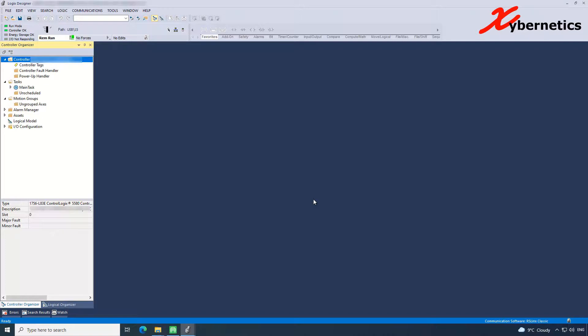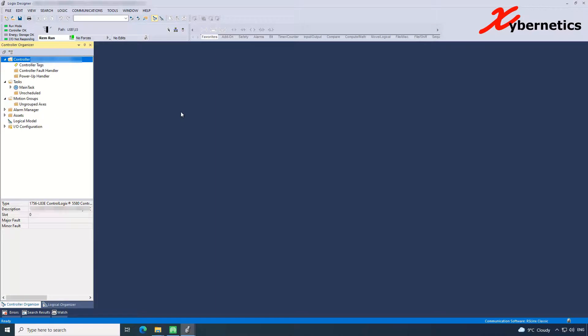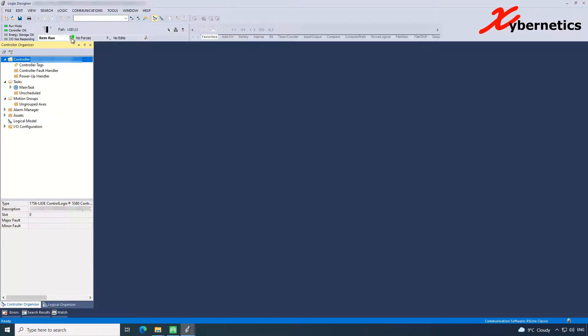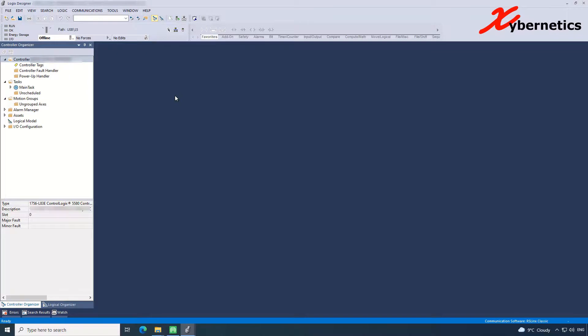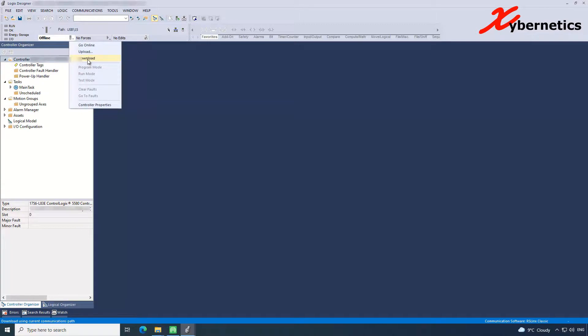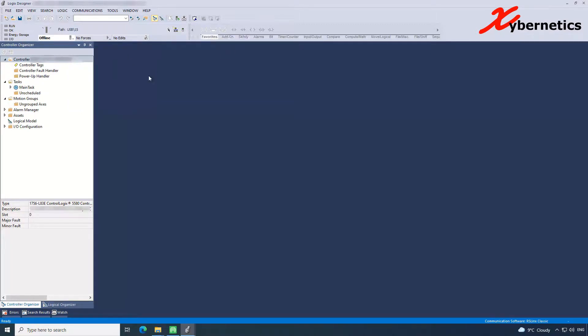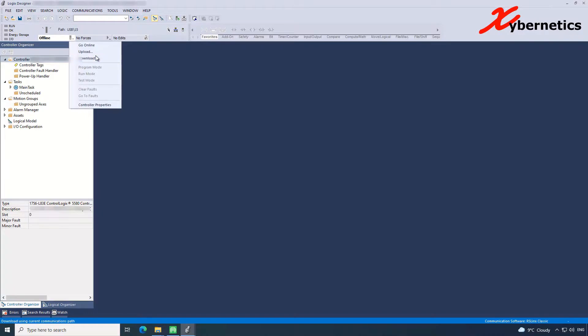So now if you want to write from the computer to the PLC, you cannot do it when you're online with the controller. What I mean by that is everything is showing green or red or whatever the status is. So I'm actually live with the controller. You cannot do a complete download. So in order to do a download, you're going to have to go offline first. And after that, once you go offline, you can either use this option here, download, or you can do the RSWHO options like I showed you just now. So that's one way to do it.